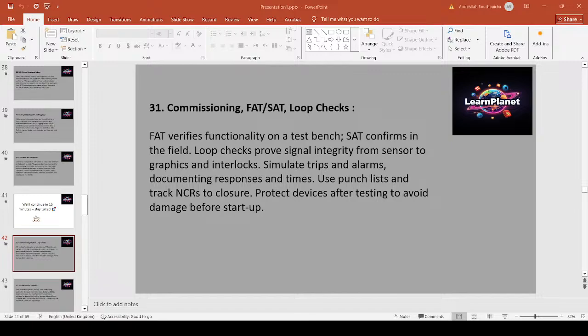FAT, factory acceptance test, verifies equipment function before shipment. SAT, site acceptance test, confirms correct operation in situ. Loop checks validate signal integrity and response from sensors to control room graphics and to interlocks. Simulate trips and document response times and operators' actions. Use punch lists and NCR tracking until closure. Protect devices after testing to avoid damage or tampering before startup. Example: a pressure loop is simulated with a calibrator during SAT to exercise alarms and shutdowns and confirm trip timing with the ESD system.